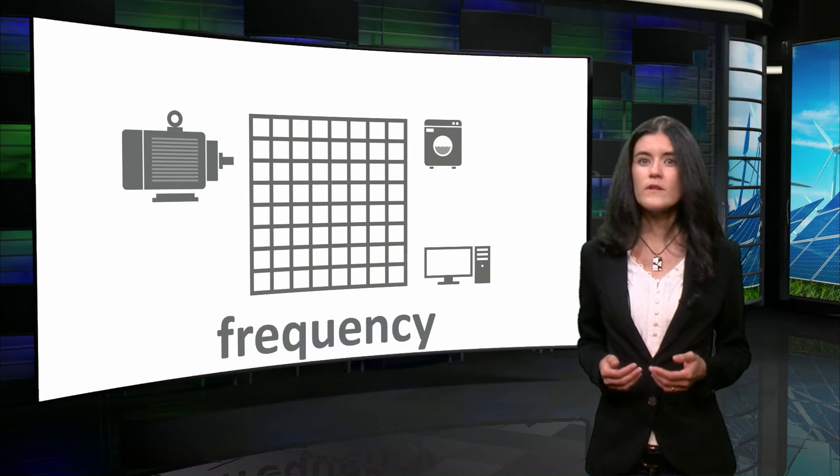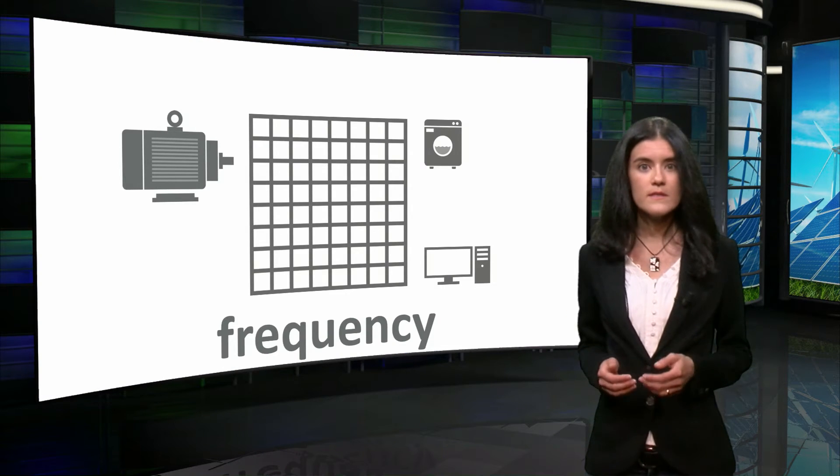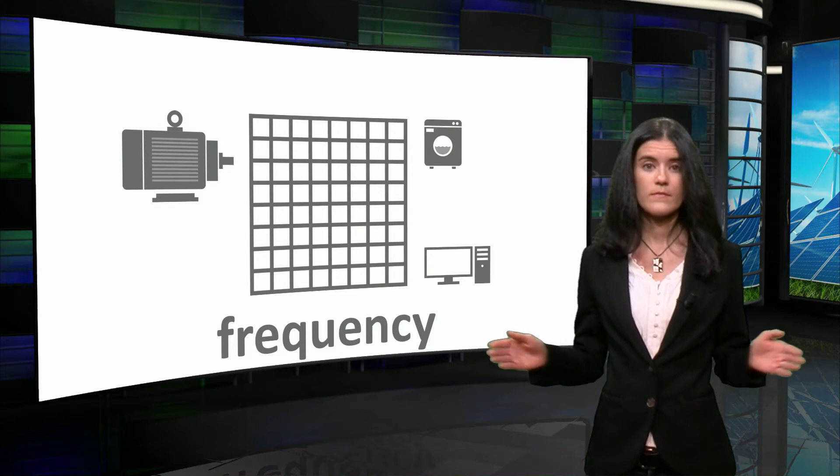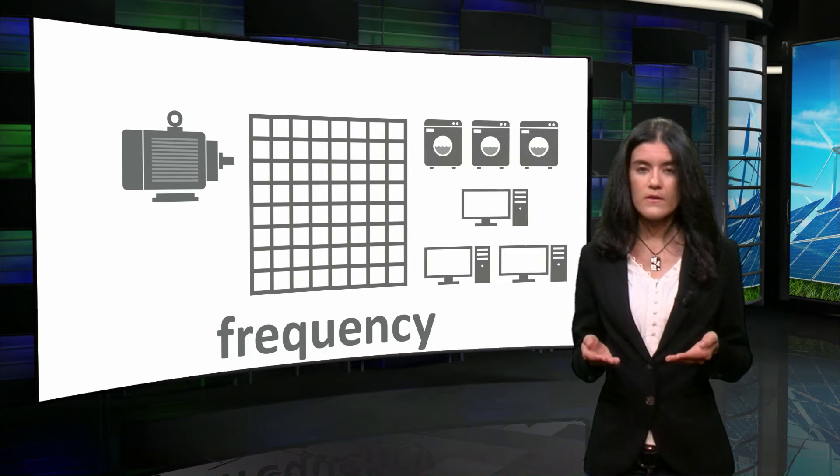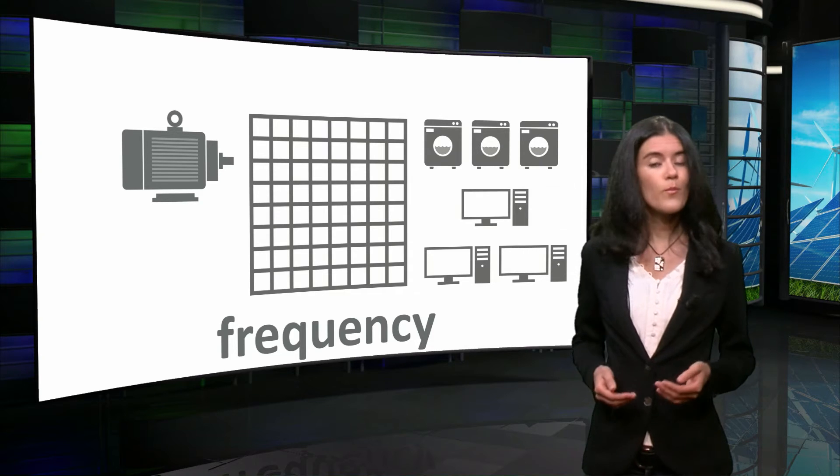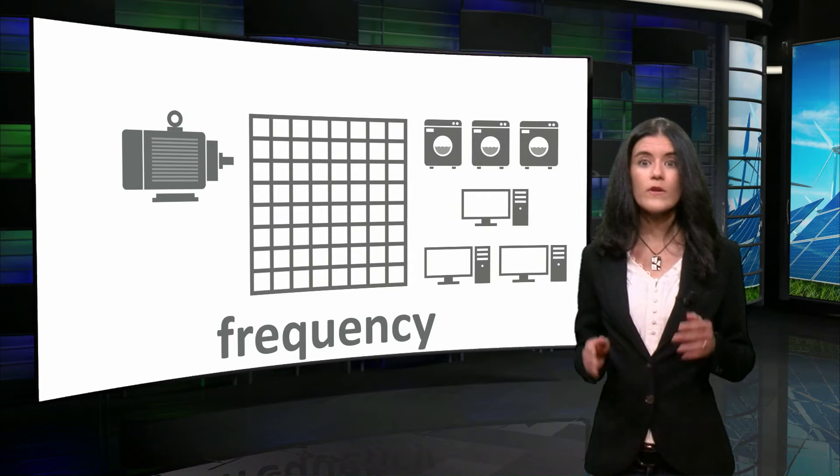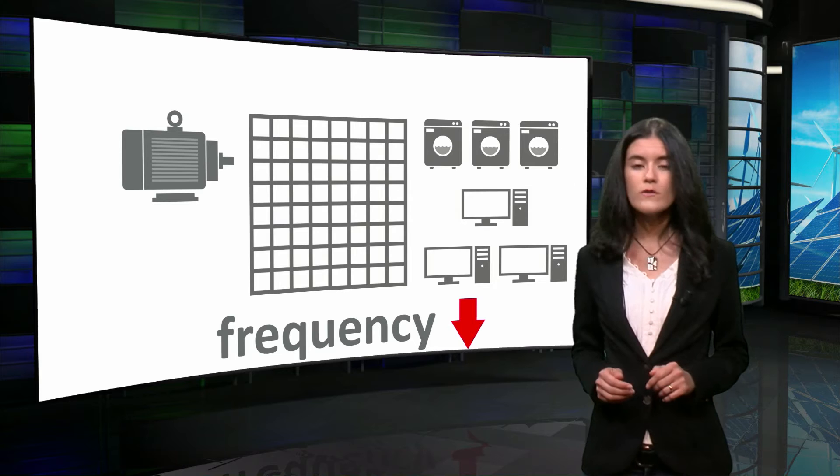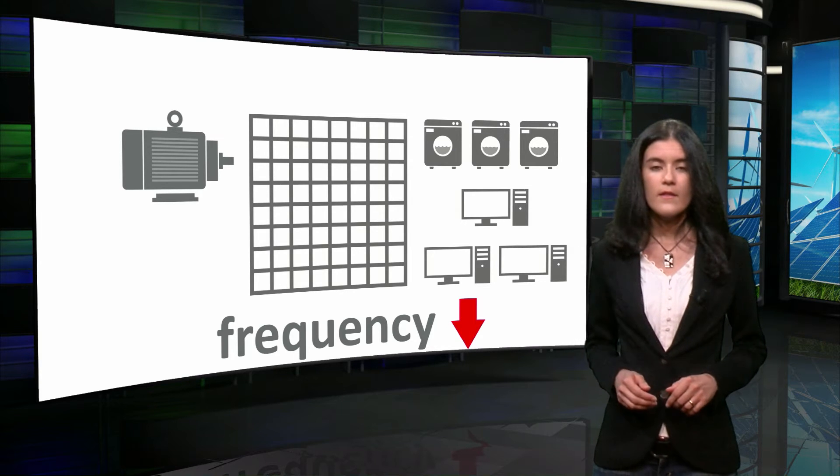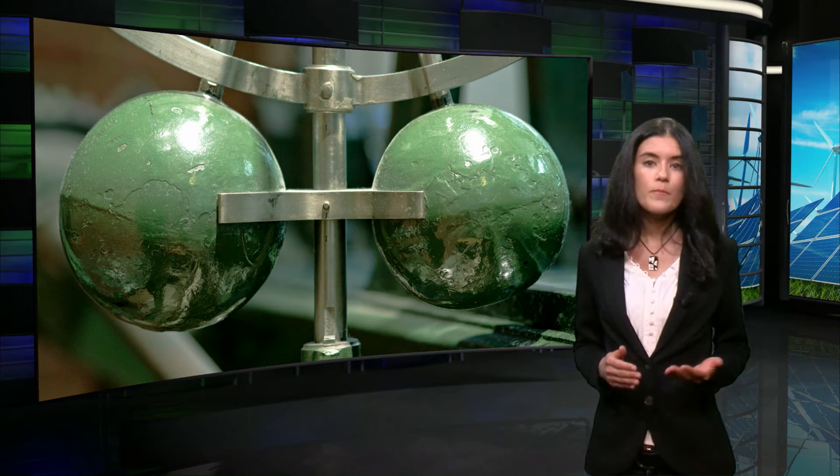It is important to mention that frequency is a common parameter throughout the network. An increase of the active power consumption, at a certain point, results in a reduction of the frequency in the whole system. The active power balance is restored by the speed governor. This action is called primary control.